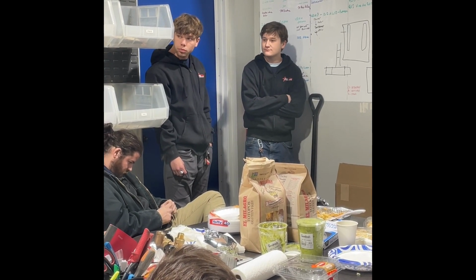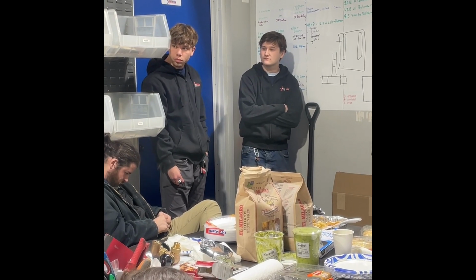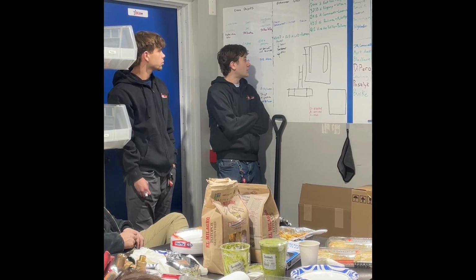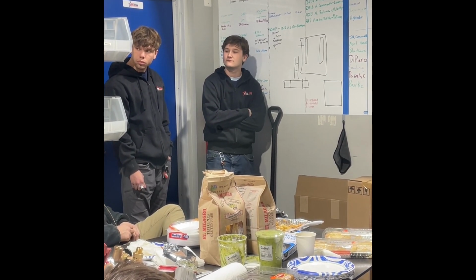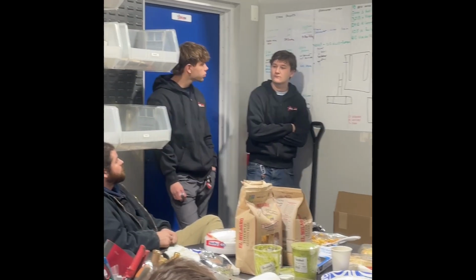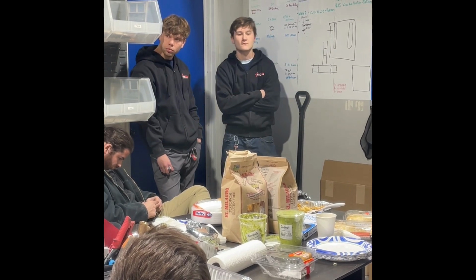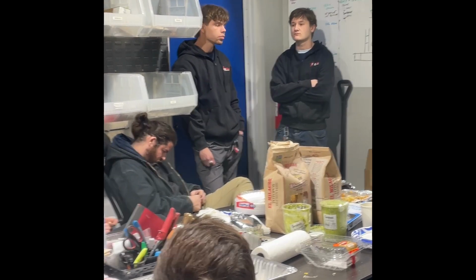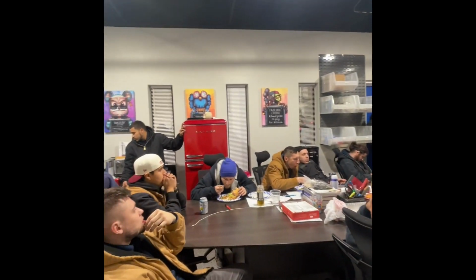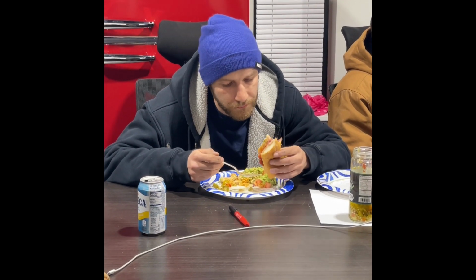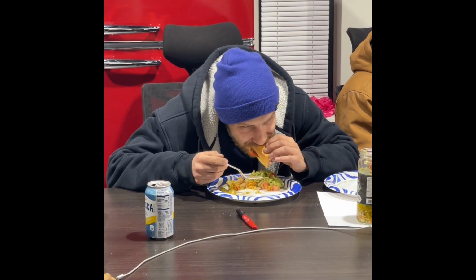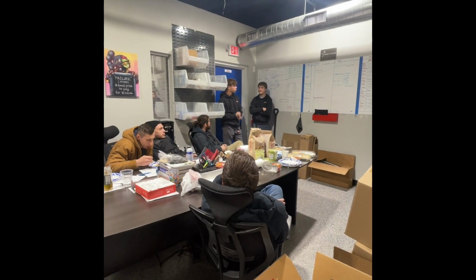So Eric, do you know why you guys had to install a transformer for the zone control board? Why would you need to install a transformer for the zone control board? Why was it necessary? You guys probably don't remember, but the Unico has its own transformer, but it only has so much power, right? We needed to install its own transformer for the control board so that it can open and close the dampers. Yeah. Right, and power up the thermostats, but mainly the dampers are motorized pieces and they require a lot of power. That's why we needed to install the transformers. Yeah, right. Because it needs to open and close the dampers. Good. That's a good explanation.